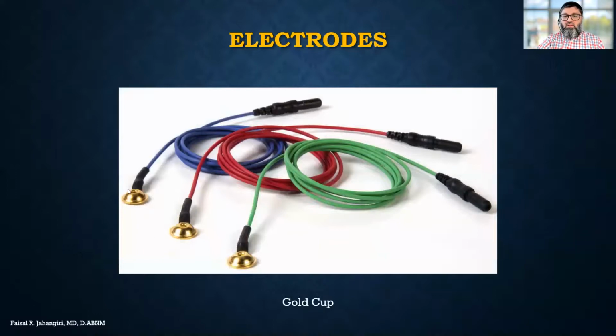The other electrode, for recording or stimulation, is the gold cup electrode. Gold cup electrodes are gold-plated electrodes in a cup shape, with a small hole in the middle where we can put paste, so if you put it on the skin, it will not have a very high impedance. You need a good conductive paste to secure it in one place. These are typically used for EEG. They are reusable electrodes; you clean them and use them again and again.